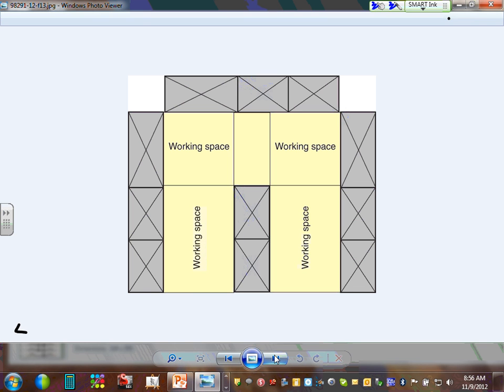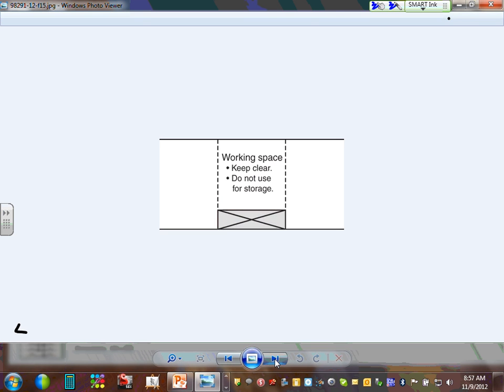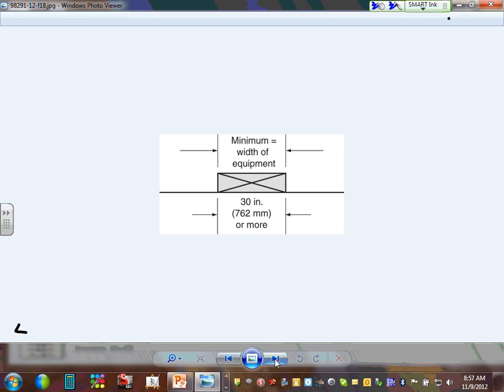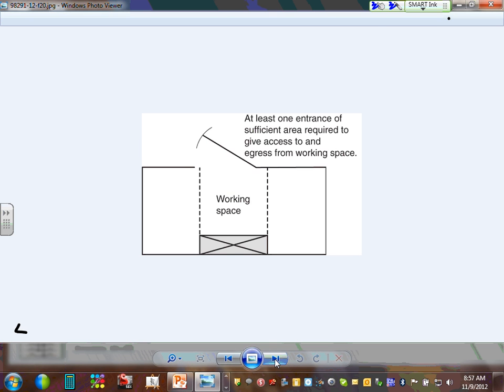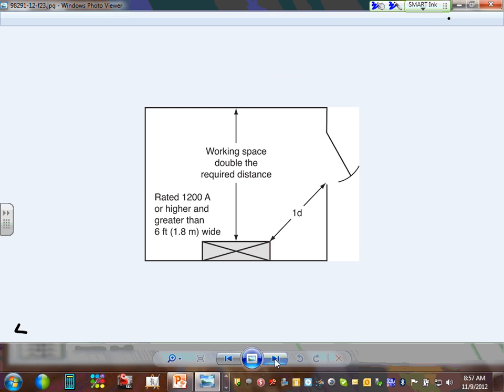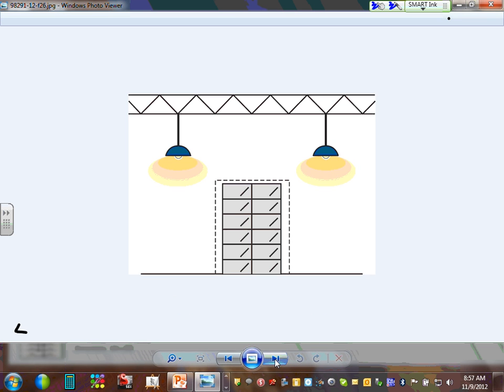So for panels, the overcurrent protection device can be inside them or outside. It has to be equal to the panel size or less. You have to label them with arc flash, interrupting rating, full load amp, voltage, and what did we say? Short circuit, the feed that feeds them, and the conductor size. Let me go directly into a couple of things about working spaces.